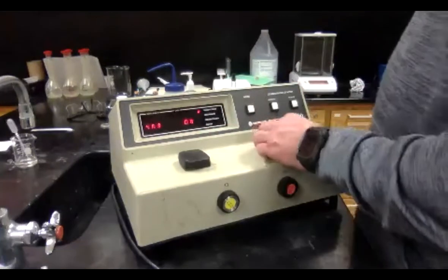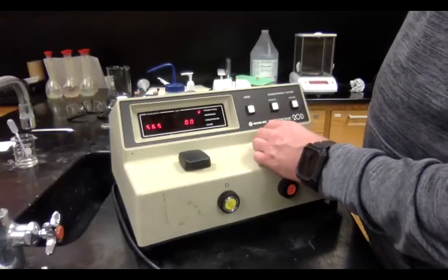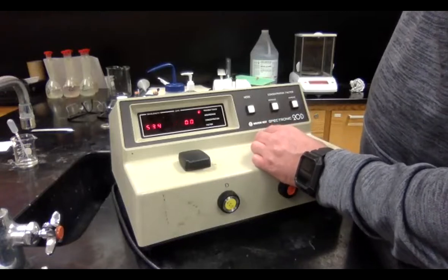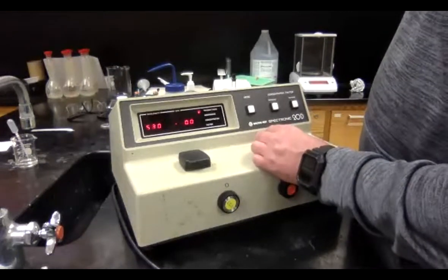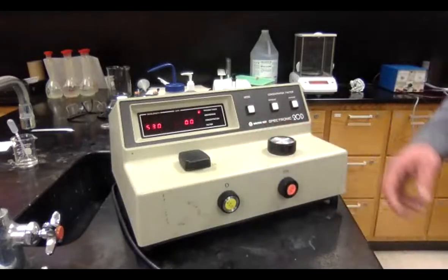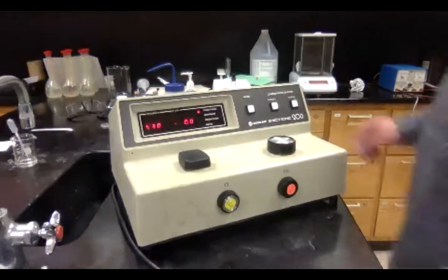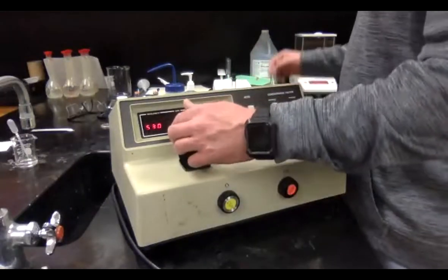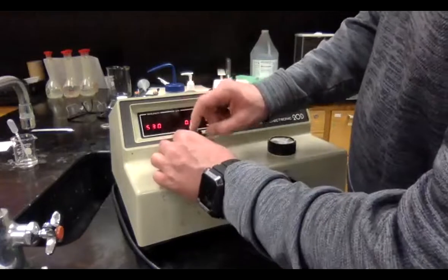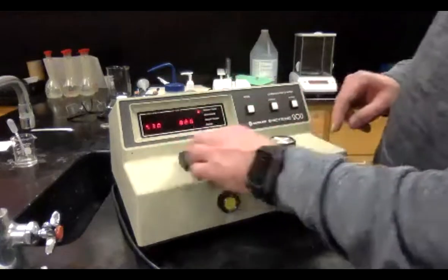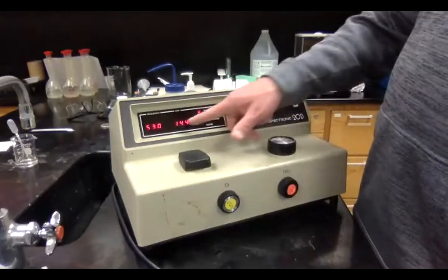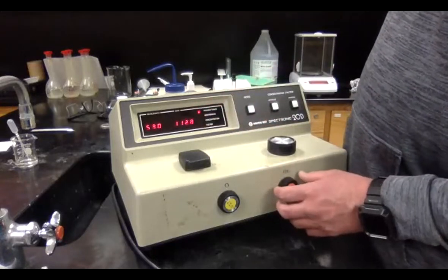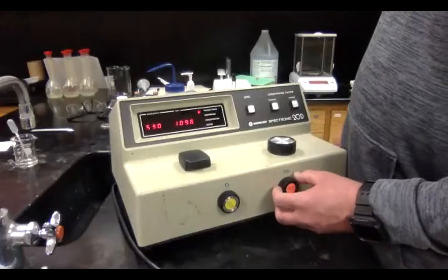So I'm going to change the wavelength. We said we could not go to 660 or whatnot. I'm going to change the wavelength from 450 to 530. We still have 0 transmittance. I'm going to pop in this guy right here. We see that we have 144, so we need to go down to 100 on that. This is again in transmittance.